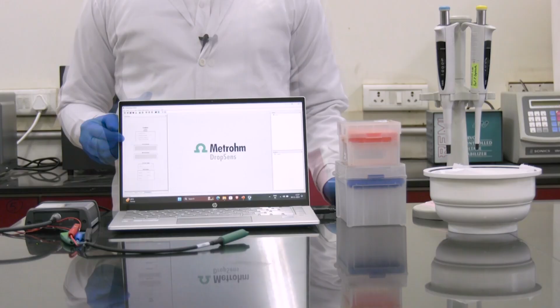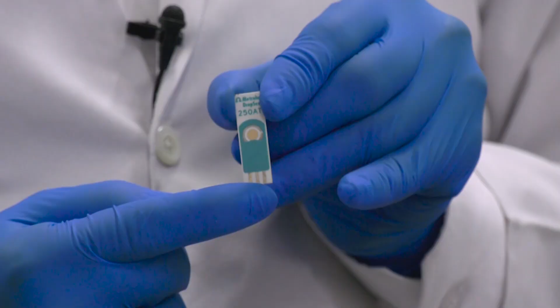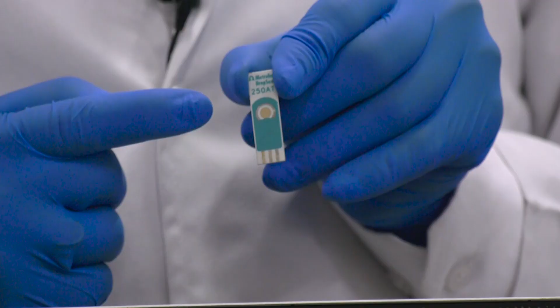This is a portable potentiostat from Metrohm, which is connected to a laptop and is controlled by software. The potentiostat has a connector for the screen printed electrode. This is a screen printed electrode which has counter, reference and working electrodes. The middle portion is the working area where we have to deposit the transducer material.